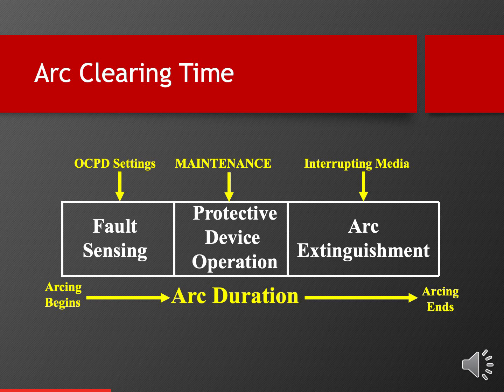It's a fault rather than just load current in the system. So that has to do with your overcurrent protective device settings, and we'll talk about that at length. But overfusing or changing the overcurrent settings can result in catastrophic arc flash events. We'll talk about that in an upcoming slide. As I mentioned, the protective device operation, how fast it actually operates, is mostly a function of maintenance. And this is true primarily of circuit breakers and the like. Fuses normally don't suffer from that problem, but normally the protective devices like circuit breakers absolutely need aggressive maintenance.